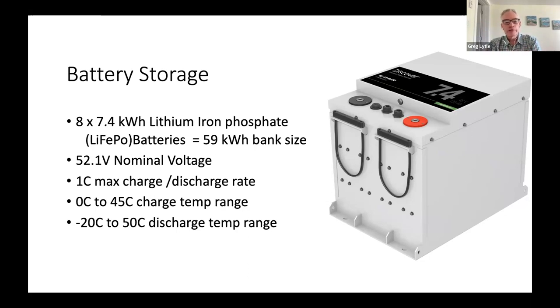Some of the other great advantages of these batteries over our older lead acid batteries is that they're effectively zero maintenance. You don't have to worry about checking water levels and topping them up and being very careful, as we had to do with our lead acid batteries in the past. That's really minimized the maintenance and made it a lot easier. You don't have the same considerations with acid and safety, or the batteries off-gassing like the lead acid batteries. They're smaller and lighter weight as well, and in practice they should have a longer service life, so they should be reliable for years to come. They also have a smart BMS integrated into the batteries, which gives improved system integration and monitoring with the balance of the system.